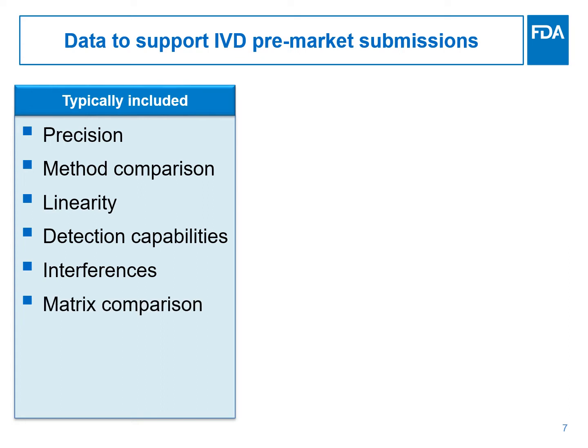Matrix comparison studies may also be submitted to support adding a sample type that is similar to the sample type used to validate the device. And reference range studies are typically included, especially for immunoassays. Each manufacturer should also provide information regarding the metrological traceability of their assays. For some devices, the special controls require annual standardization by a certifying organization, and I will come back with some examples in the next slides.